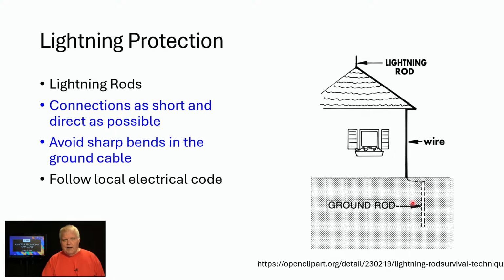We mentioned lightning protection. And what it is actually to try to discharge, hopefully slowly, any static buildup in the atmosphere, number one. That's one of the ways that lightning rods work, is to have a small trickle current come down to ground. The other is if lightning is going to hit it, well, okay, direct the path of the lightning strike. And if you're going to have a lightning strike, you want to make sure that the connections are all tight, clean, and are short and direct as possible. You want to avoid sharp bends in grounds for lightning protection.